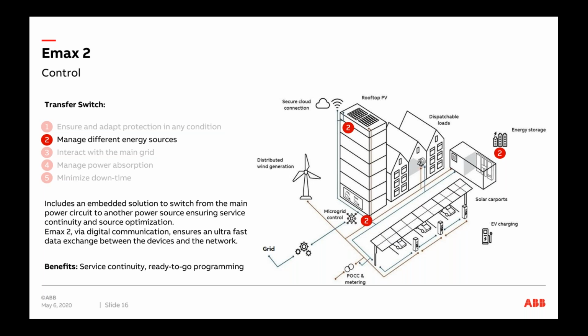So it's quite straightforward. We communicate between the two Emax 2s protecting the main source and the alternate source, and they communicate with each other through our eKIP link communication protocol. And we have something we call the synchro check module, which allows us to synchronize power supplies from the two sources and have a smooth transition. Now, speaking of transition, we can look at either a closed transition setup or an open transition setup. So that's possible with Emax 2.